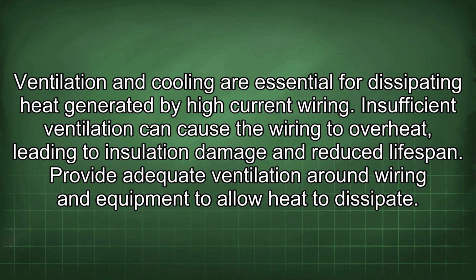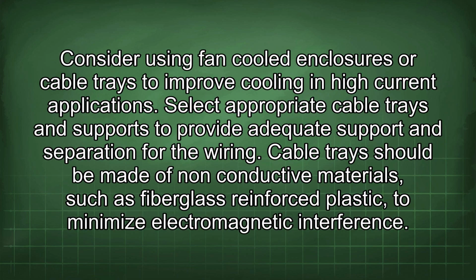Ventilation and cooling are essential for dissipating heat generated by high current wiring. Insufficient ventilation can cause the wiring to overheat, leading to insulation damage and reduced lifespan. Provide adequate ventilation around wiring and equipment to allow heat to dissipate. Consider using fan-cooled enclosures or cable trays to improve cooling in high-current applications.